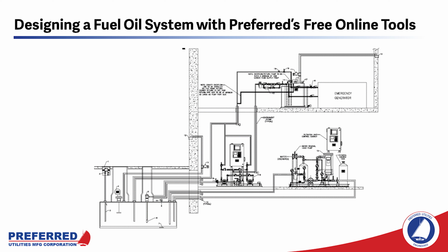So this is what we're talking about. It's a system that supplies one or more emergency generators, topping off either day tanks or belly tanks, using a transfer pump set that's pulling from either underground storage tanks or above ground storage tanks.